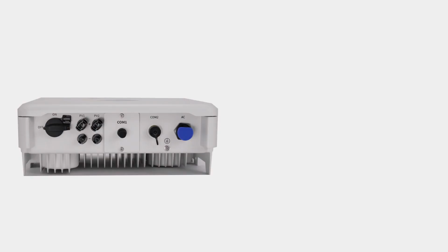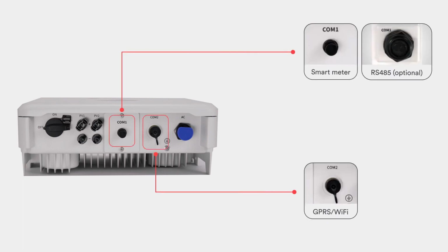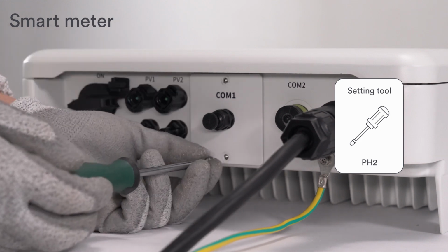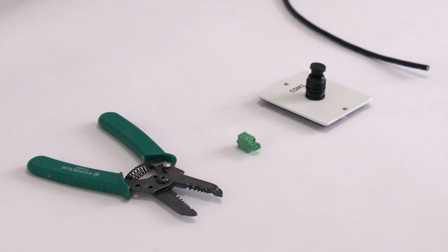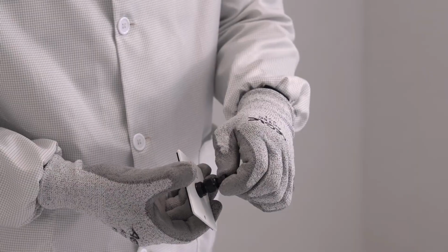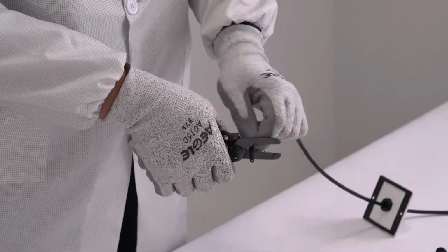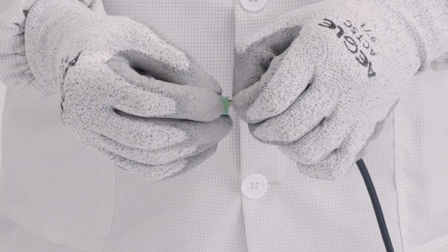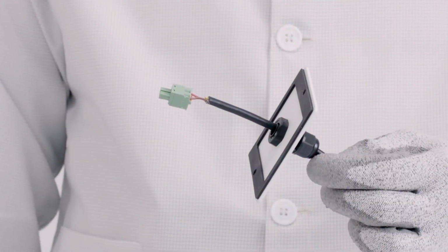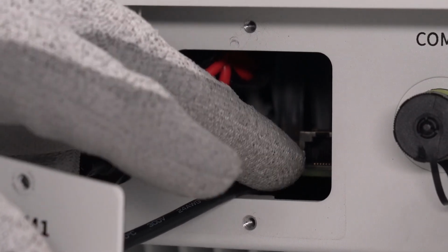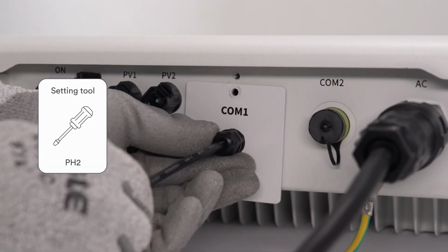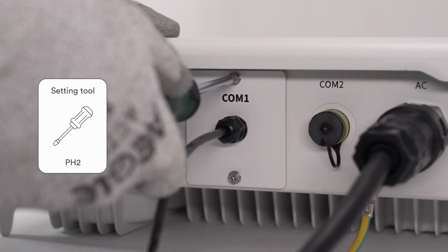Solplanet Single Phase Inverters provide 3 different modes of communication, depending on the installation region: smart meter, RS485, and Wi-Fi or GPRS stick. This can, based on your requirements, be chosen during the order process. Remove the communication plate from the inverter. Loosen the swivel nut of the cable gland on the communication plate. Remove the sealing plug and lead the stripped cable through the cable gland and communication plate. Press the latch of the smart meter terminal and insert the stripped cable accordingly. Make sure the cable is connected firmly. Insert the smart meter terminal to the socket. Attach the communication plate to the inverter with M4 screws and tighten the swivel nut.